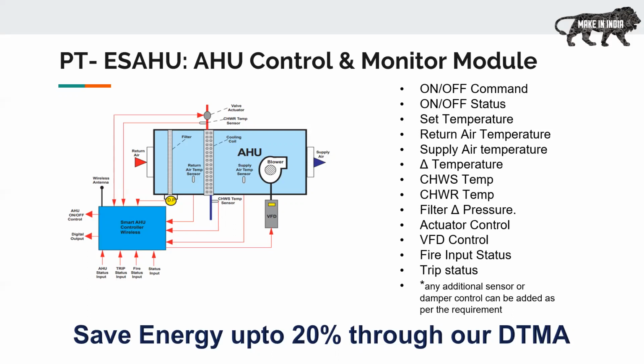And then we have your VFD control, 0 to 10 volt VFD control, fire input status, trip status, and like that. Now to this module, we have a provision to add on multiple sensors, such as if a client requires a CO2 monitoring system or a PM monitoring system, or they want to control the fresh air dampers, we can add on an additional module and connect it. As I proceed further into the presentation, I will highlight the key features through a pictorial representation of the module.